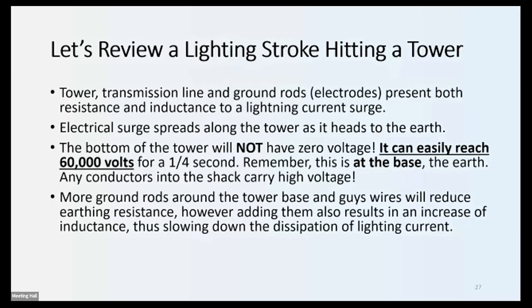By the way, the conversation we just had here in the room was that a couple folks suggested, and Bob here suggested, that the first ground rod away from the tower should be the length of the rod away from the tower. After that, it should be double the length of the rod if you're using 8-foot rods, 16 feet.